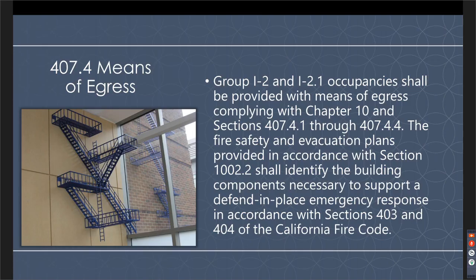There are, of course, egress requirements, and you've used Chapter 10 for your general egress requirements, but 407 has specific requirements for the I-2 occupancies. So you still use 10, but you have to use the specifics here. And in 407, there are, well, let me see if we're there yet. I won't go there yet. We have these specific requirements because we have a defend in place system. So in most occupancies, if the fire alarm goes off, there's an event happening, the occupants can get up, get out.